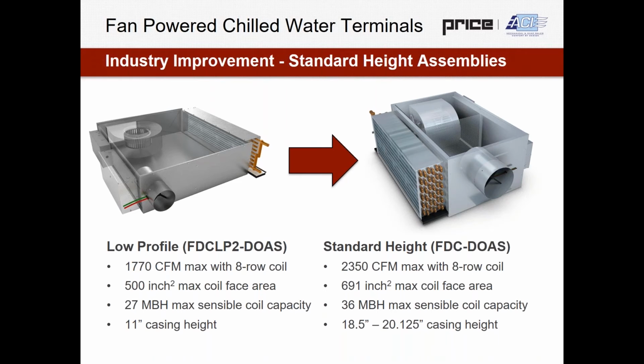Well, a larger casing height results in much higher airflow ranges. It's also going to result in a much larger max coil face area. So a taller coil without sacrificing too much width on that coil face. And the result there is much more sensible coil capacity, which can be delivered to the space. So this means that equipment can be consolidated for value engineering and cost improvements for projects.